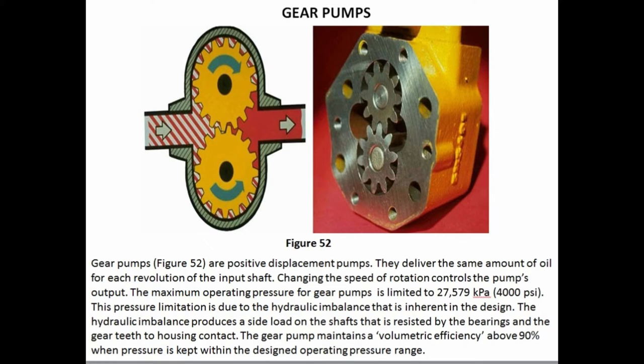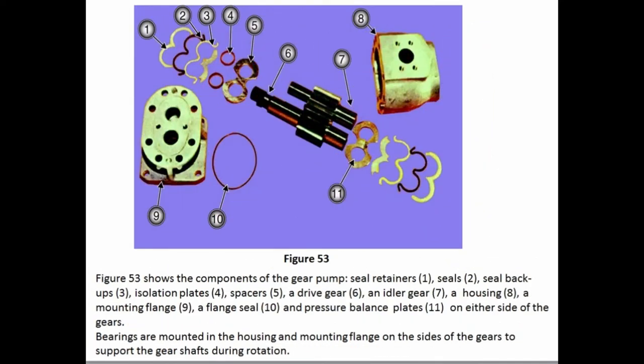Gear pumps (Figure 52) are positive displacement pumps that deliver the same amount of oil for each revolution of the input shaft. Changing the speed of rotation controls the pump's output. The maximum operating pressure for gear pumps is limited to 27,579 kilopascals (4,000 PSI). This pressure limitation is due to the hydraulic imbalance inherent in the design. The hydraulic imbalance produces a side load on the shafts, resisted by the bearings and the gear teeth-to-housing contact. The gear pump maintains volumetric efficiency above 90% when pressure is kept within the design operating pressure range.